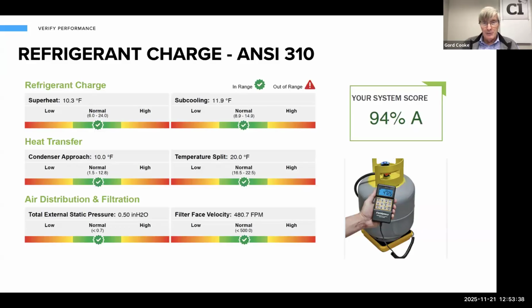For example, this system is working at 94% of its rated capacity. Some homeowners are going to say, I want 100%. Fair enough. Let's tweak it. But wouldn't it be nice to know that you're able to achieve, the day you move in, the day the system is commissioned, that it's working correctly? And I would put it on your list of things to do. If you're going to go all electric and you're going to be at heat pumps, and you are, then you would say, I want to add this. I want to make sure my mechanical contractor or my certified energy rater is able to do this testing to verify for your clients that the system is working correctly.